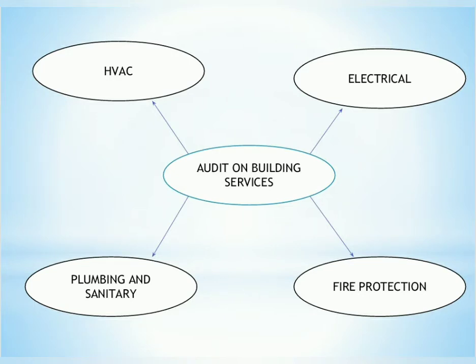The identified electrical system defects in the UTEM Healthcare Center are: A, general performance and hazards; B, transformer; C, cable wiring; D, distribution equipment; E, protective device, lighting, standby emergency power, grounding and lightning protection system; and earthing defects. Integrating predictive maintenance and maintainability issues at the design stage could maximize the electrical system efficiency as well as the effectiveness of the performance throughout the building's life cycle.